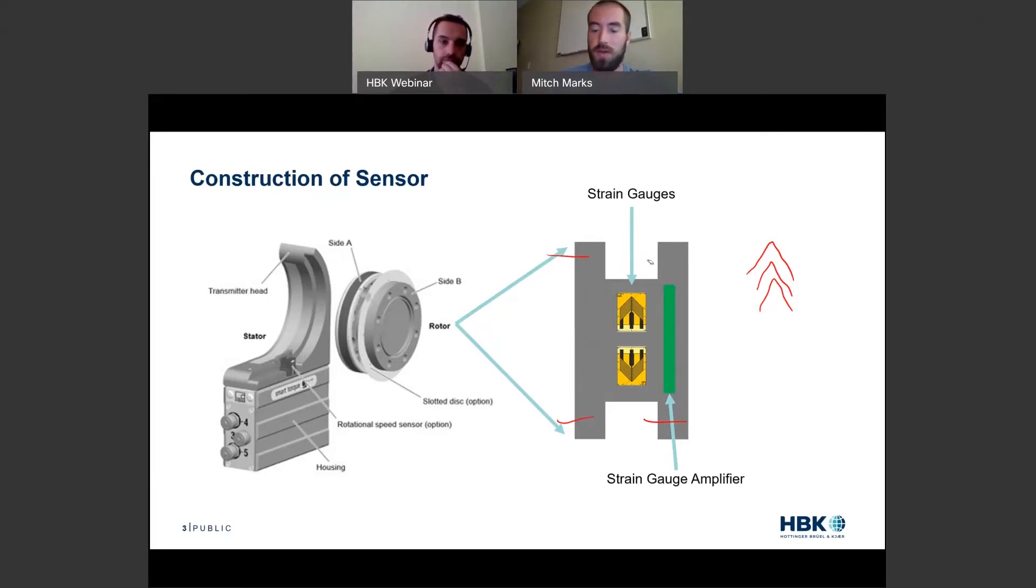Now anybody who's spent any time around strain gauges knows that it's not just the gauge that matters, it's not just the material it's on, but it's also the amplification, the excitation, and the compensation. We have a little circuit board indicated by this green here, where we are providing power to the gauges. We're compensating for things like rotational speed, temperature, linearity, and hysteresis effects of the metal.